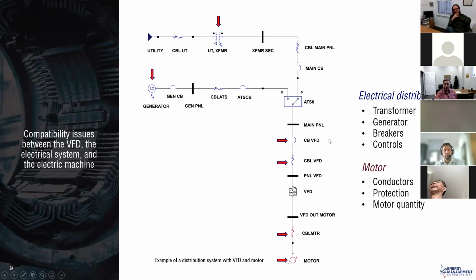Circuit breakers, you know that the waveform can have a higher peak and sometimes can have nuisance circuit breaker issues. And then the VFD itself and the cable to the VFD and the motor are all things we hope to touch on a little bit, as they relate to what you might need to know that could be affected in other parts of the system once you've added this device, the VFD. And I'd have to say that I give a presentation like this with a little bit of trepidation because I don't want to insinuate drives are problematic. Drives are very commonplace and very commonly installed nowadays, and the problems we're talking about are not the norm. If we install a drive nowadays, there's probably very little chance of dV/dt issues with inverter duty motors and so forth. But we've encountered problems in all of these areas, and we'd like to discuss that just a little bit.